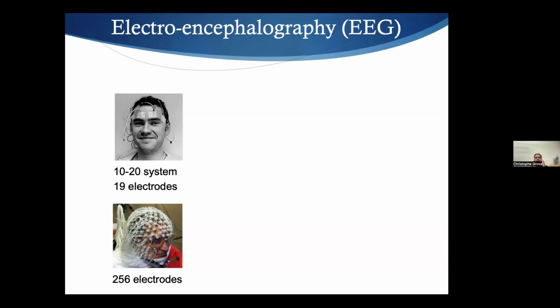We ask for the lower temporal electrodes because the 10-20 is really not covering some part of the temporal lobe. And that's also a problem with some of the commercial EEG caps that you see mainly for application in psychology. Some will stop there and you are really losing some. So now most of the caps are more high density and they will cover nicely all those regions.